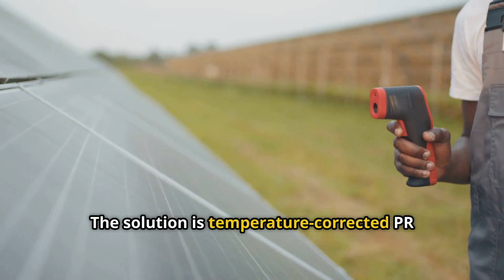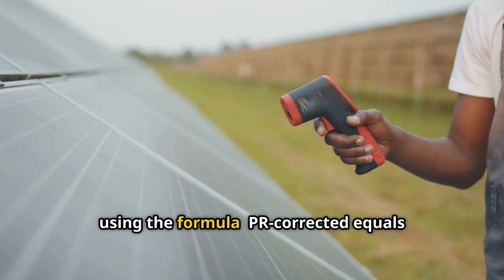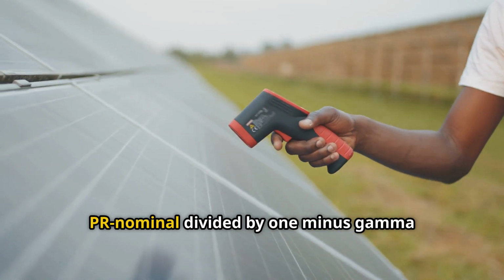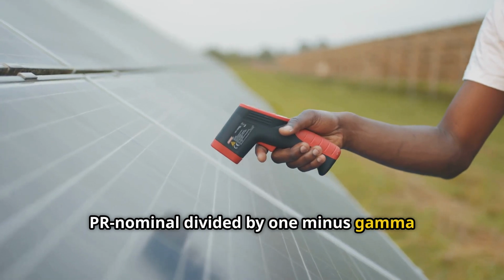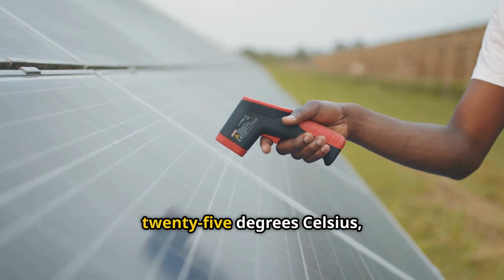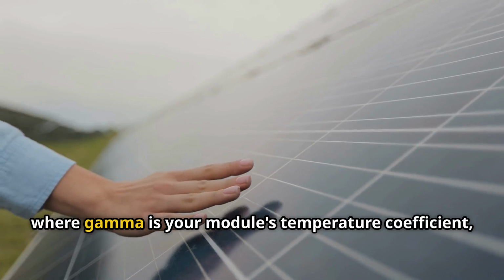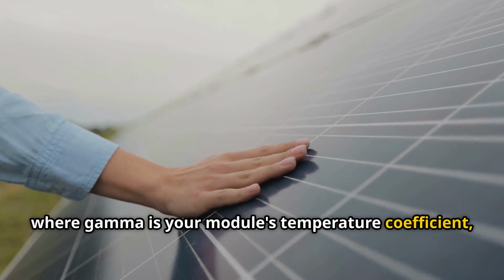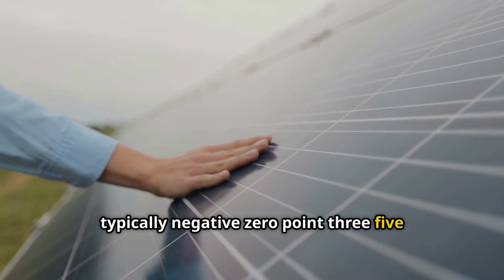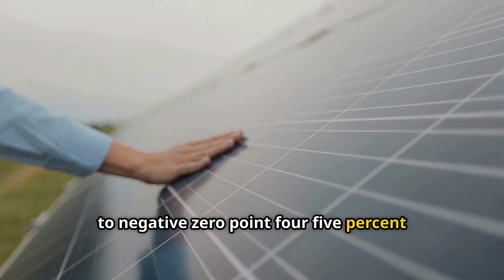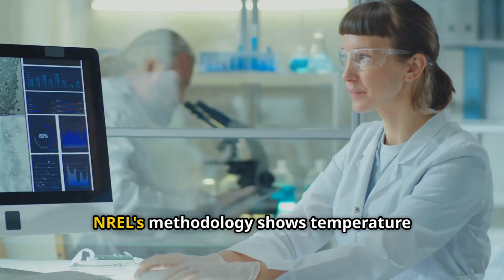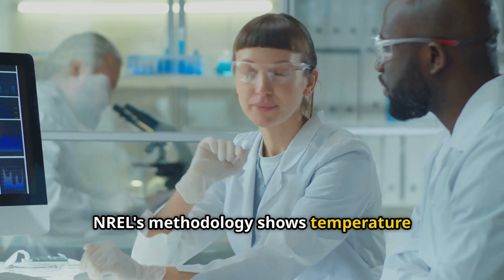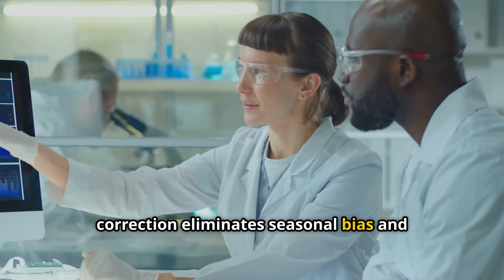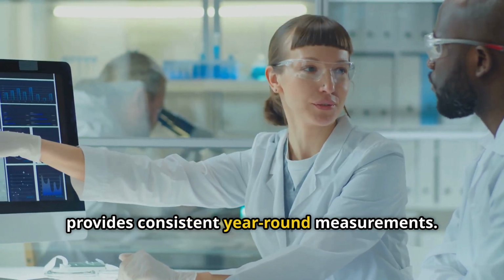The solution is temperature-corrected PR using the formula PR corrected equals PR nominal divided by 1 minus gamma times the cell temperature minus 25 degrees Celsius, where gamma is your module's temperature coefficient, typically negative 0.35 to negative 0.45% per degree Celsius. NREL's methodology shows temperature correction eliminates seasonal bias and provides consistent year-round measurements.